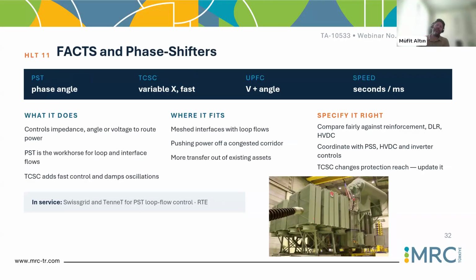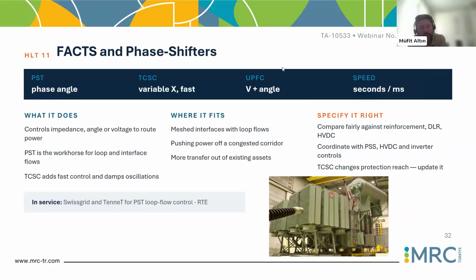This I put as generic: you can think of the flexible AC transmission devices. Phase shifters, again, you can control both the impedance and the angle at your connection point or in your corridor. Then you will have more power to transfer, or if you have some oscillations, you can damp the oscillations depending on your needs. This is again more specific, series connected devices.